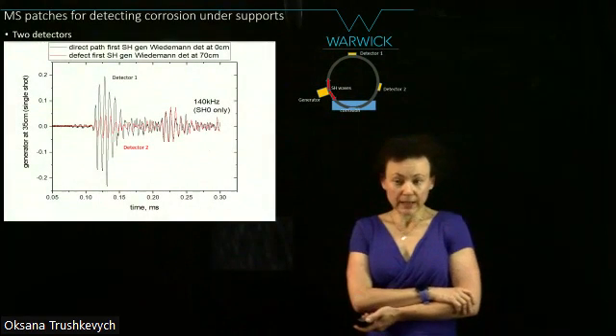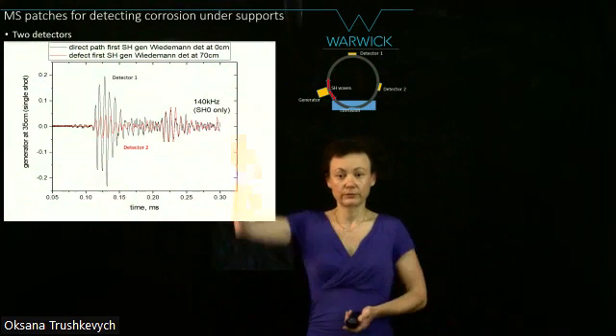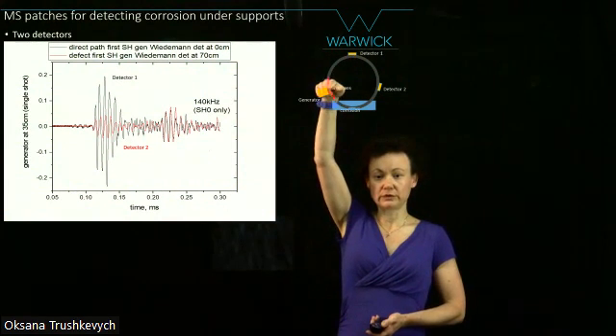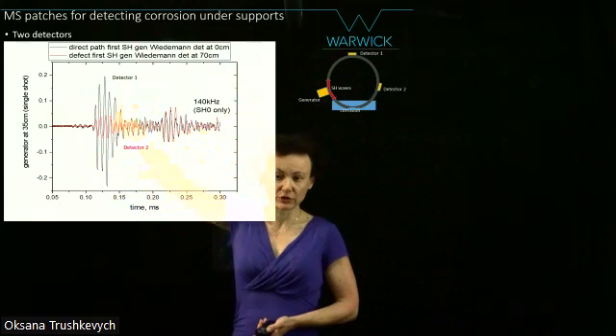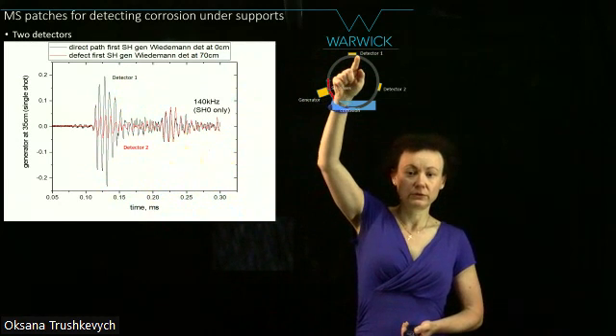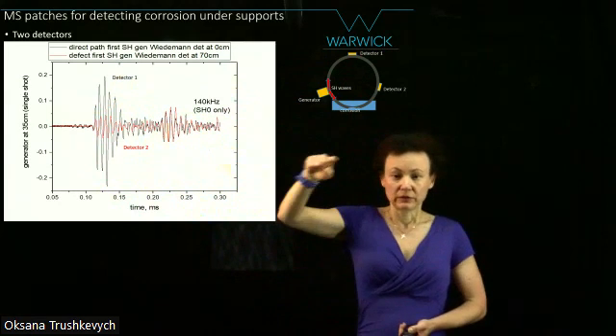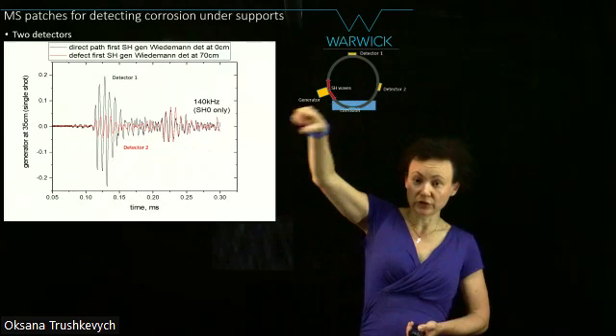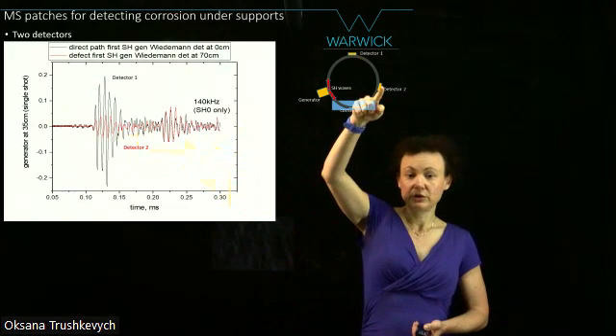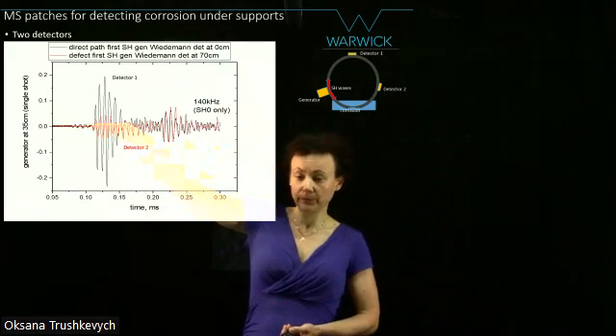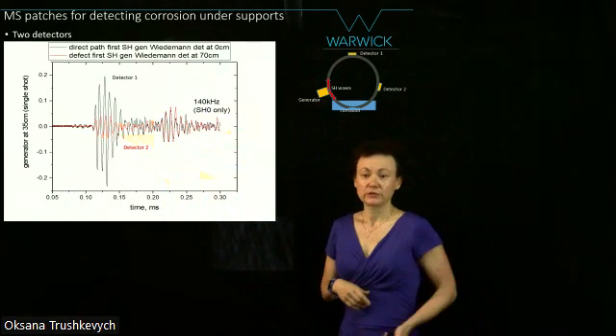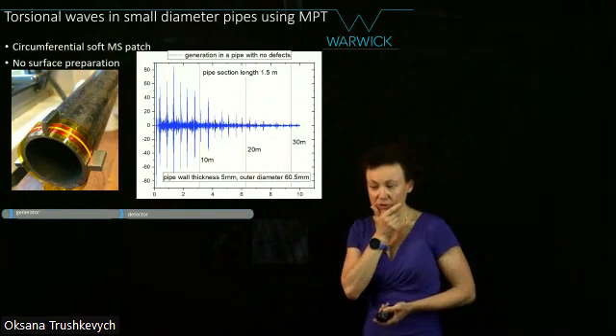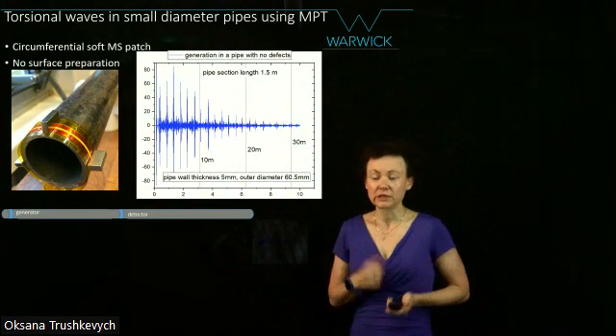The black trace is taken at detector 1. It first gets the signal, that big peak, which is the shear horizontal SH0 wave mode. It comes from here and hits that detector, that's our big peak. At the same time, in the other direction, we send the same type of wave, but because it passes through the corroded region, only a small amount reaches detector 2. That's the second peak. So we can detect corrosion on the supports, install them permanently, and just come and read the data when we need to.